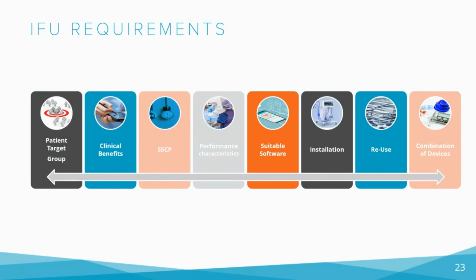Secondly, the format of the IFU must be user friendly and easy to understand. This includes the use of clear and concise language, the use of diagrams or illustrations to explain complex procedures, and the inclusion of summary sections highlighting the key points. Thirdly, the language used in the IFU must be in the official language or languages of the country or countries where the device is being marketed.